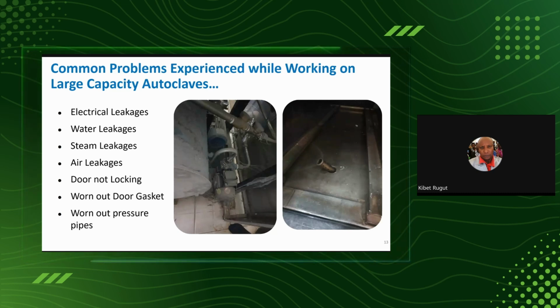The solenoid and the plunger sometimes could be stuck. The gasket, because of the many times you open and close, can get worn out and compromise the pressure in the chamber. And then pressure pipes can also get worn out through maybe even natural corrosion. And so it is good to watch on them. It's just a diagram of areas where you can easily see any type of faults that I mentioned above.